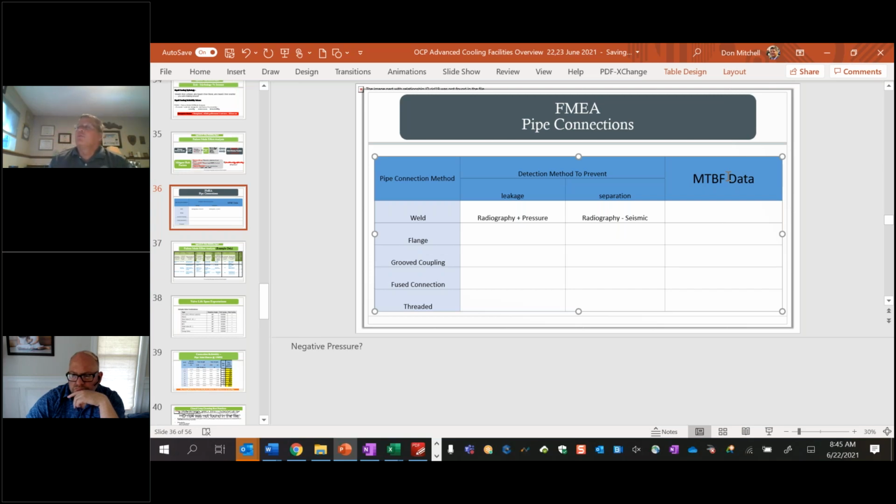Okay. This is MTBF. Hear me out. MTBF is a statistical measure. Why do you say it's electronic? MTBF works with any manufactured product, electrical or anything else, but if you go through the science, if you have a very repeatable process where you can drive out the defects, the fundamental thing you're saying today is that you don't use it on welds because weld is artwork, and much of pipe is artwork, and that's why you can't use MTBF. MTBF is a random failure rate, and it has a specific statistical meaning. People tend to take MTBF and put it onto mechanical things, which is totally incorrect and misleading. So you have to be very careful.